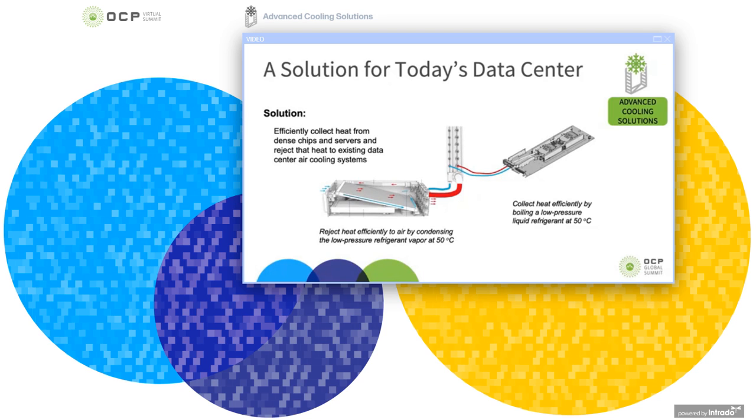The evaporators placed in parallel on all of the processors in the rack efficiently collect the heat. Small 6 millimeter tubes direct the vapor from the processors to the refrigerant distribution unit, or manifold, which then passes the vapor to the heat rejection unit, or HRU. The HRU contains fans that blow cold aisle air across a condenser, forcing the refrigerant vapor to give up its heat and condense back to a liquid. A pump then draws that liquid out and pushes it back to the evaporators, where the cycle begins again.